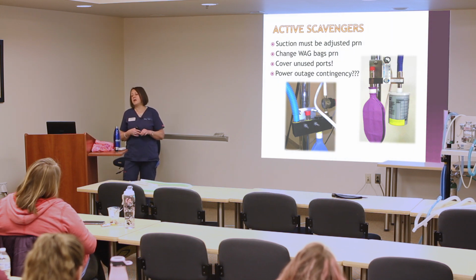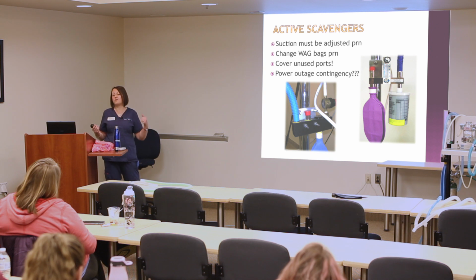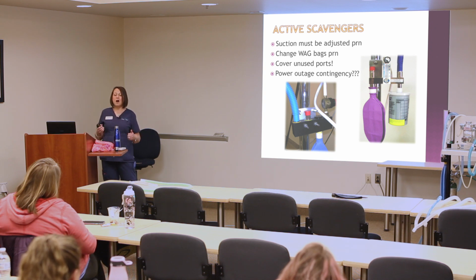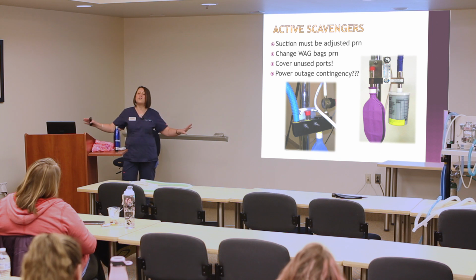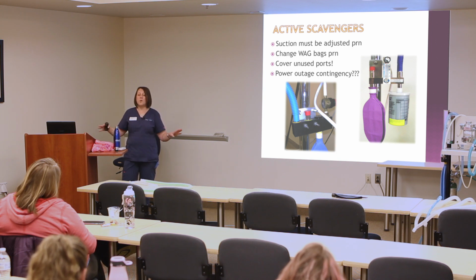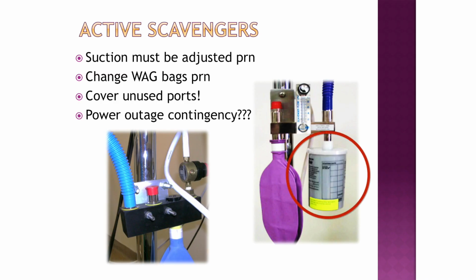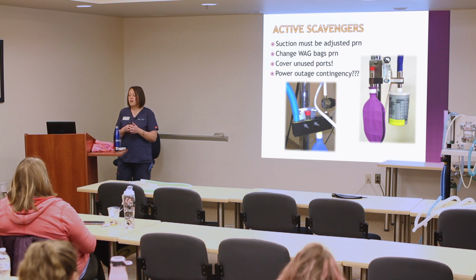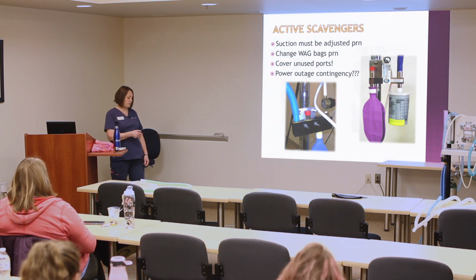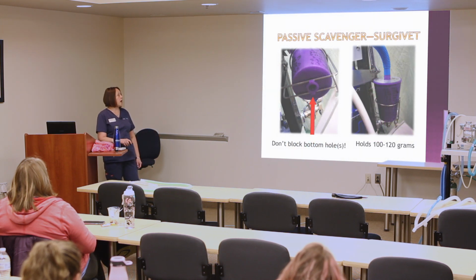And if you're doing an anesthetic case and your machine is hooked up to the active scavenger plugged into the wall, you can assume then and there that it's not working. And all of the waste anesthetic gases are going to be coming into your room. So as soon as the power goes out, make sure that you grab one of these F-air canisters and hook it up onto your scavenger hose. The purple Surgivet canisters are able to fit both the 19 and 22 millimeter hose, so it is likely that it will fit.